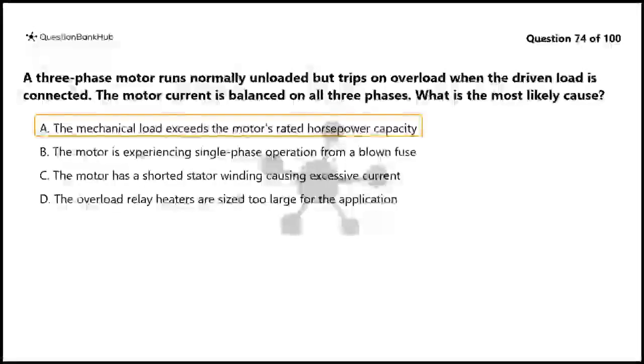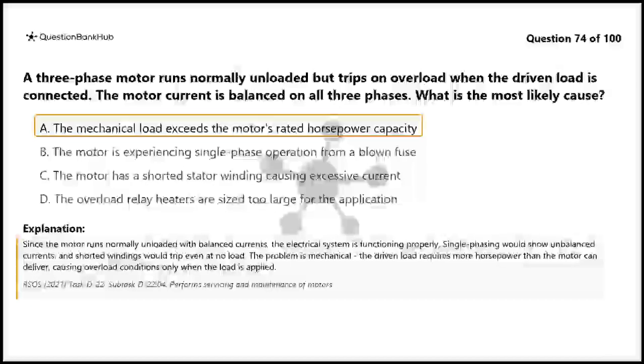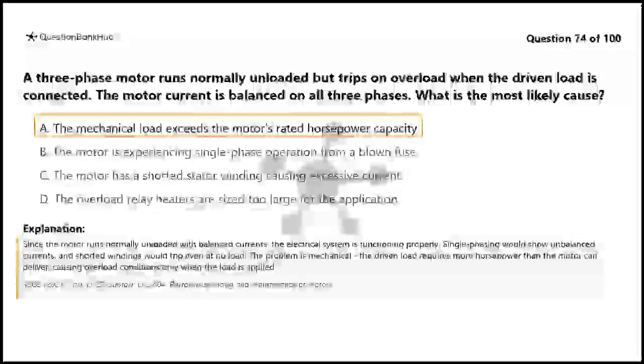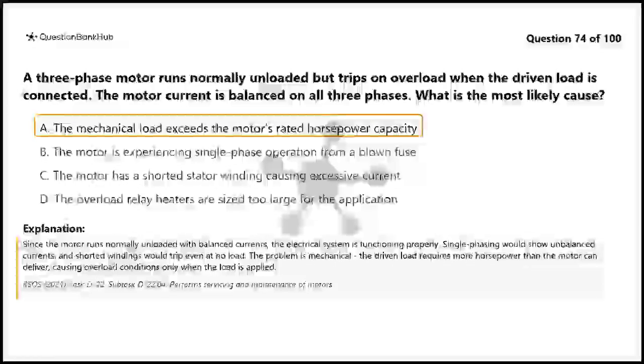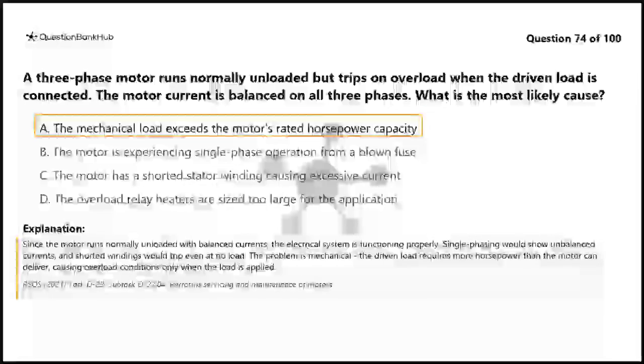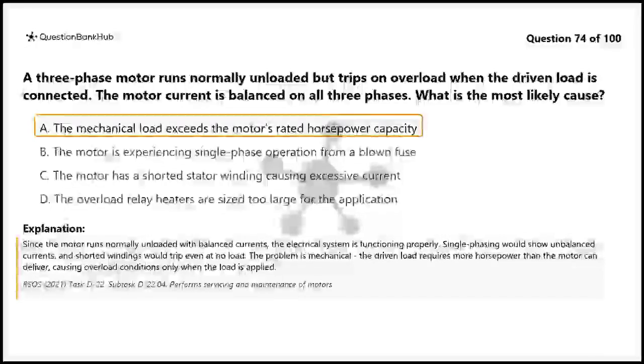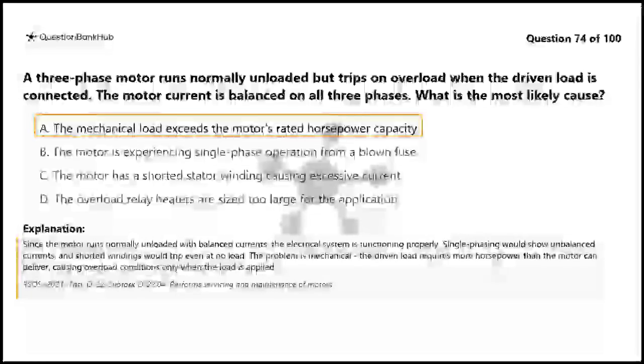The mechanical load exceeds the motor's rated horsepower capacity. Since the motor runs normally unloaded with balanced currents, the electrical system is functioning properly. Single phasing would show unbalanced currents, and shorted windings would trip even at no load. The problem is mechanical. The driven load requires more horsepower than the motor can deliver, causing overload conditions only when the load is applied.